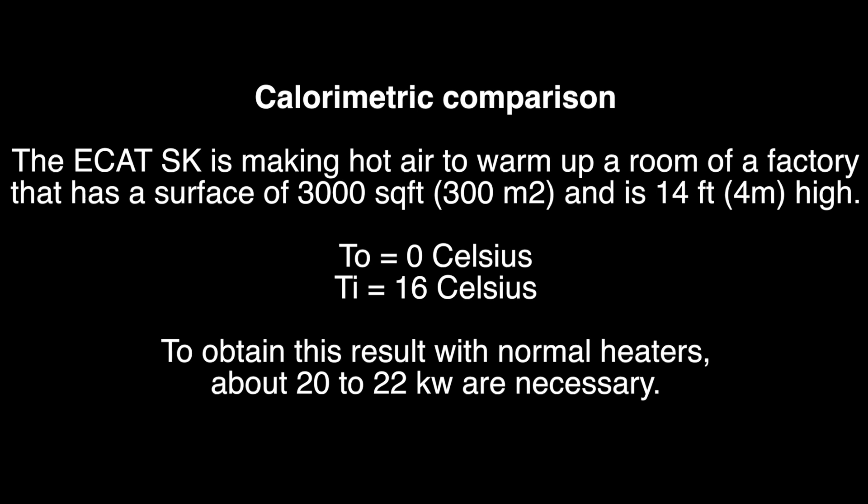For the T outside, the calculation that was made when the temperature was 0 degrees Celsius outside, or 32 degrees Fahrenheit, the room temperature was about 16 degrees Celsius, which is about 61 degrees Fahrenheit. To obtain this result with normal heaters would require between 20 and 22 kilowatt rating. So, you would need a boiler of about 20 to 22 kilowatts of power to heat up in these conditions with these results.